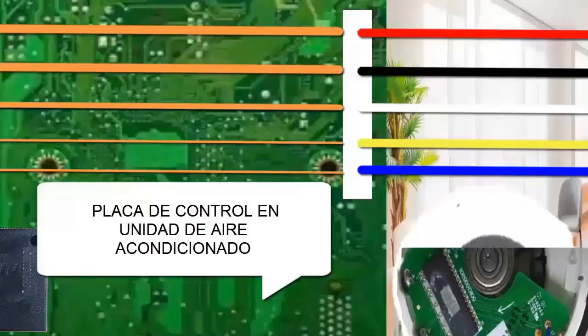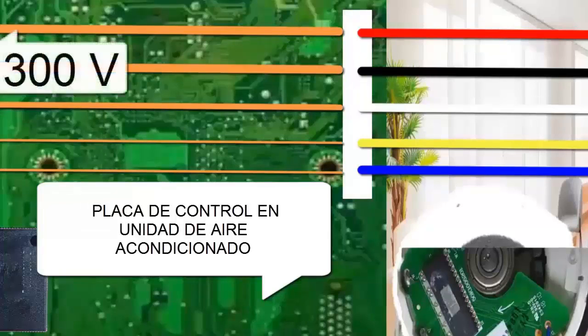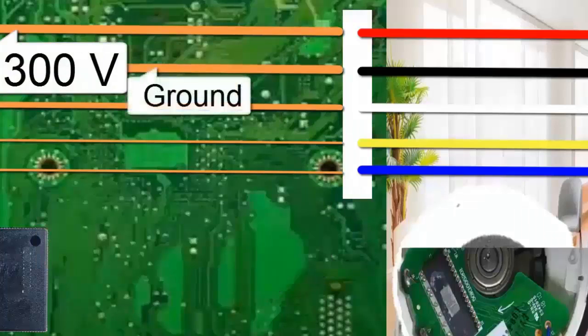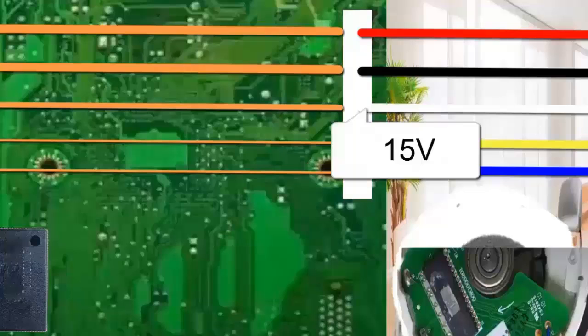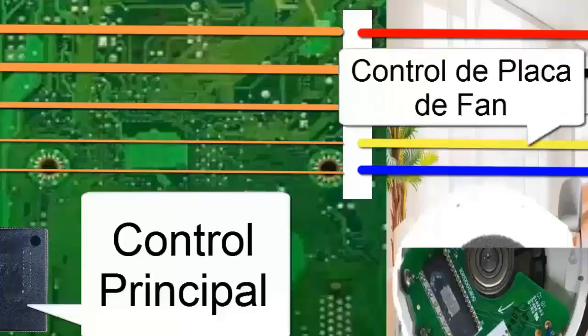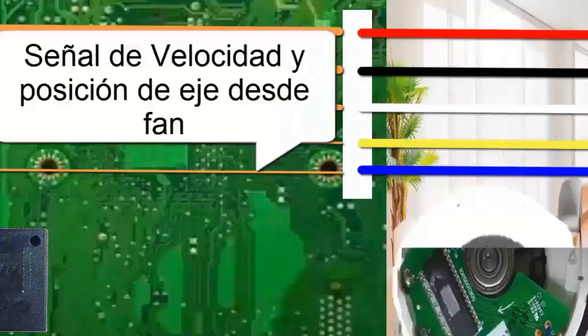C. These 5 wires are generally identified by specific colors. Red, high voltage DC power supply, approximately 300 V when the mains power is 220 V. Black, ground or common for the entire electronic board. White, power supply to the internal electronic controller of the BLDC fan, usually powered with 15 V. Yellow, signal or pulses from the main board controller to control the internal motor board of the BLDC. Blue, signal from the BLDC motor to the main electronic board to indicate the speed and position of the BLDC motor rotor.